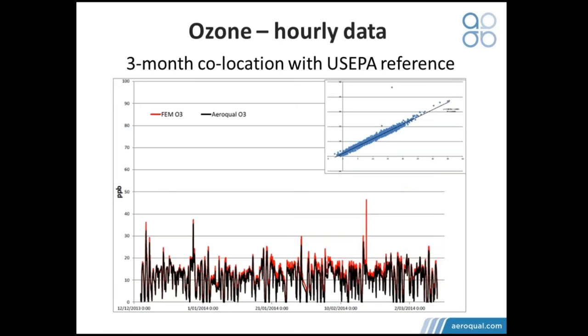Here's a similar slide showing the ozone data for similar reasons. The red is the reference method, and the black is the Aeroqual ozone module, and you can see a very close correlation between the two instruments. So what does this kind of data tell us? It shows that this kind of instrument is very reliable and can be used for near-reference studies and monitoring, which is one of the primary applications for this instrument.